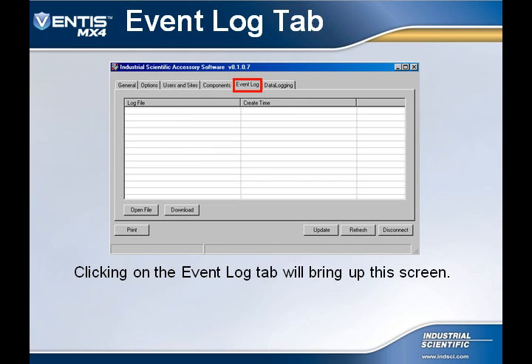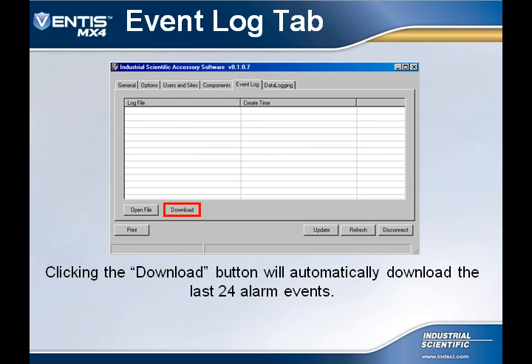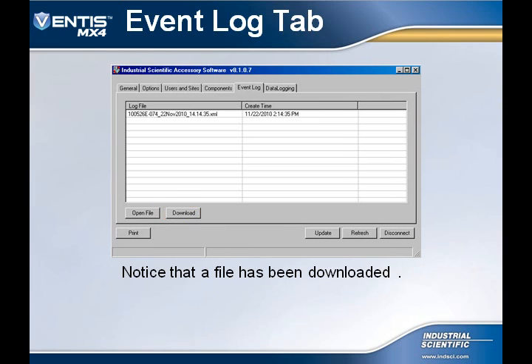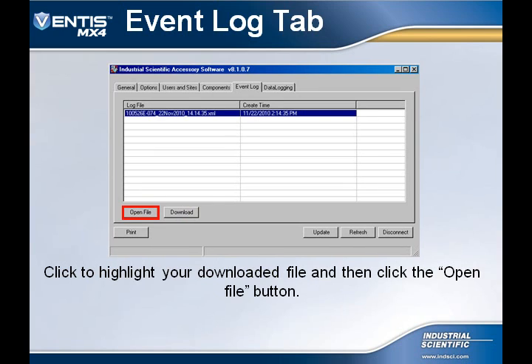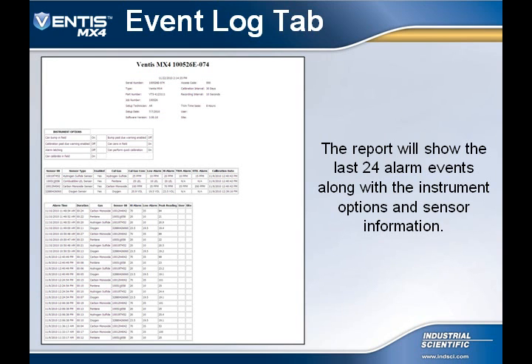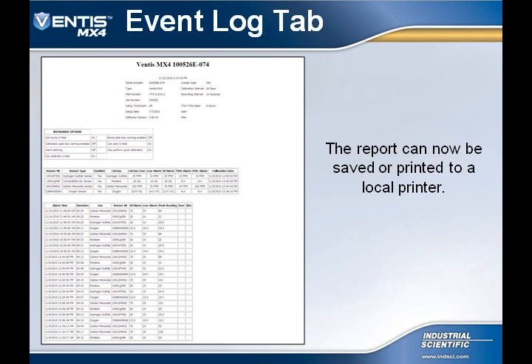Clicking on the Event Log tab will bring the user to this screen. This tab allows downloading, viewing, and printing of logged events stored in the instrument. Click on the Download button to download a file of the last 24 alarm events. After the download, a file will appear in the log file. Highlight the downloaded file and select the Open File button to view all stored alarm events. This report shows the alarm time, alarm duration, sensor that went into alarm, sensor serial number, high and low alarm set points, and the peak reading. Active user and site information will also be shown if entered. This report can be saved or printed if a hard copy is desired.